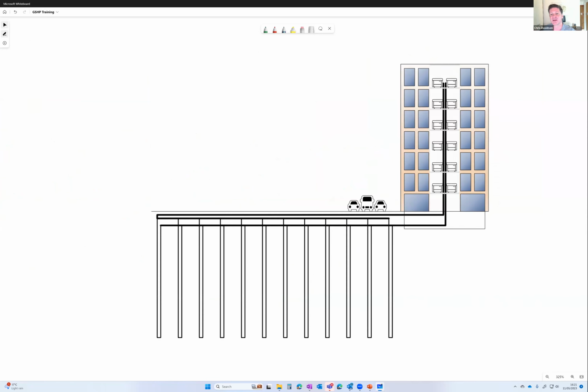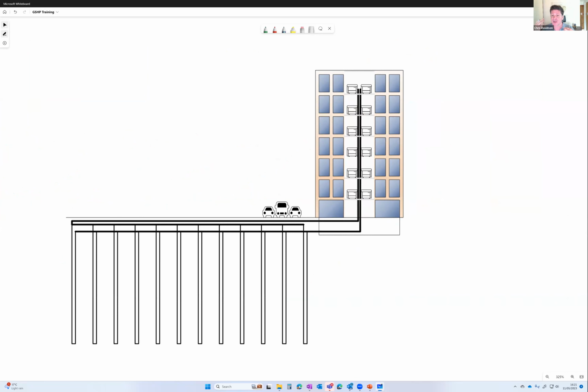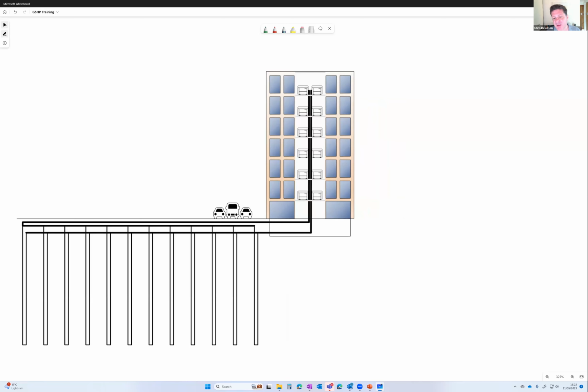So let me contrast that then by looking at a distributed heat pump system, very often called an ambient loop, sometimes called a fifth generation heat network, although the definition of fifth generation heat networks is far from universally agreed in the industry. So what we've got now is, first thing you can see is we've got no central plant there at all. We don't even have central circulation pumps on these systems. And that's really important because we've got no central run costs for the system. What we've got in each dwelling though is a heat pump, and that heat pump can turn on to do our domestic hot water at our 65 degrees C, but it can then turn off doing domestic hot water and drop to the 35 degrees I mentioned earlier to do that space heating.